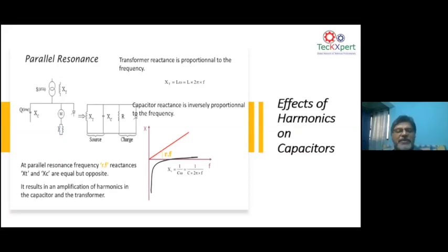So now what happens whenever you have an LC combination in a power system depends on what frequency is in the network. At 50 cycles, if you put capacitors, you will not see resonance, because capacitors are generally used to improve power factor at 50 cycles. You don't use capacitors to improve power factor at 250 cycles and 350 cycles, because at those frequencies the capacitor loses its property and will start getting overloaded.